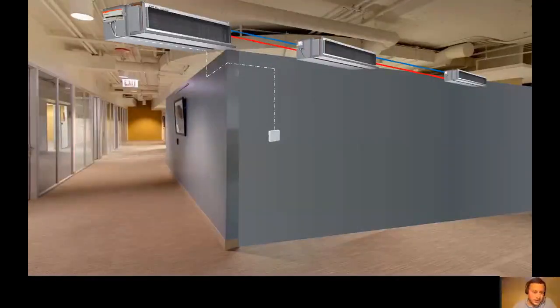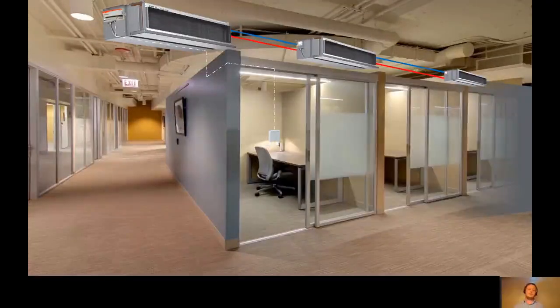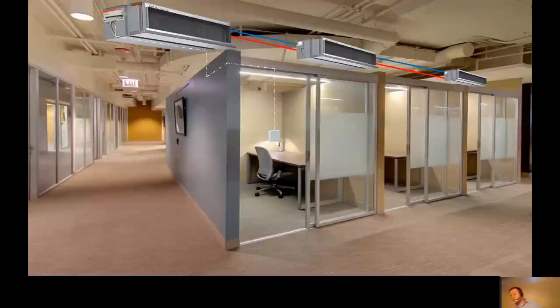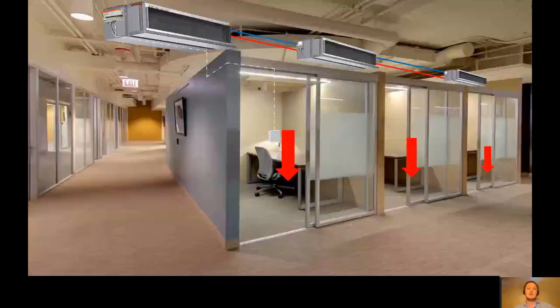Next thing that happens is they change the dynamics of the room to now have 3 satellite offices or cellular offices. Problem with that is that the sensor's still in that same location. It's in the one office. It's not in the other offices, and now we have an issue of a mismatch, because the requirement in that first office is that it wants heat, and that means that the other 2 offices have to heat as well. So what would we have to do there? Well, quite simply, we'd have to put a master controller on each of the other 2 units and put a sensor in the same 2 offices so that you're effectively individually controlling each unit.